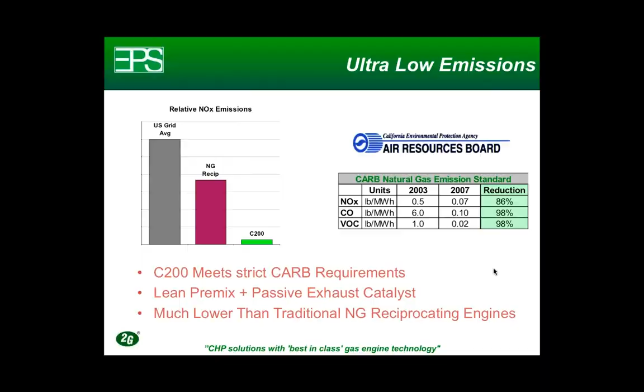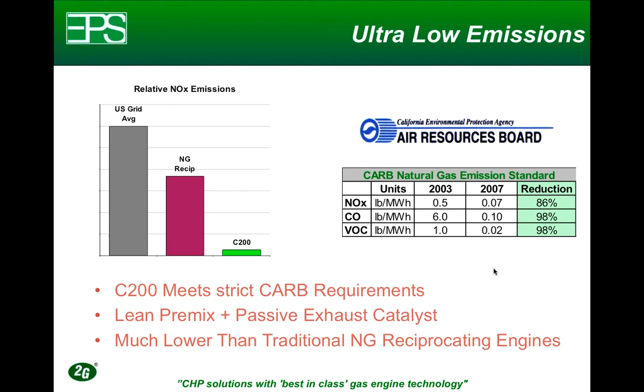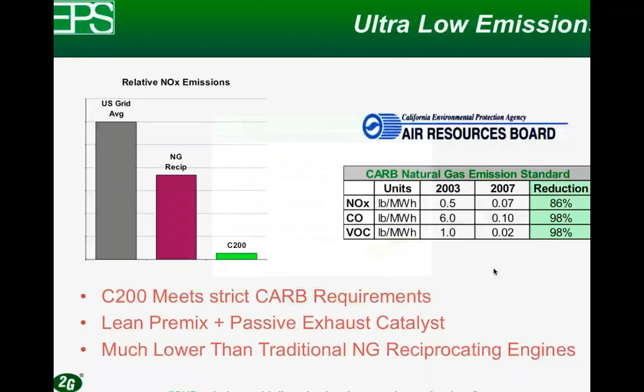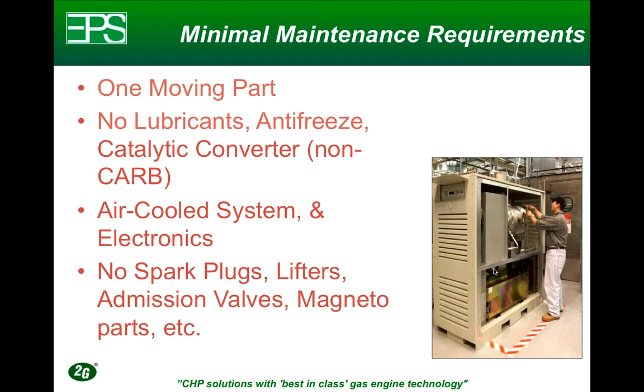Their claim to fame is very, very low emissions. Reciprocating engines today do require exhaust cleaning, as I talked about earlier. Microturbines have extremely low emissions and can be installed without any additional emission control requirements. Additional benefits are that the unit does not require any lubricants, no antifreeze, no oil. It's basically an air bearing where the unit spins. There are far fewer parts that require maintenance than what you would see on a reciprocating engine.